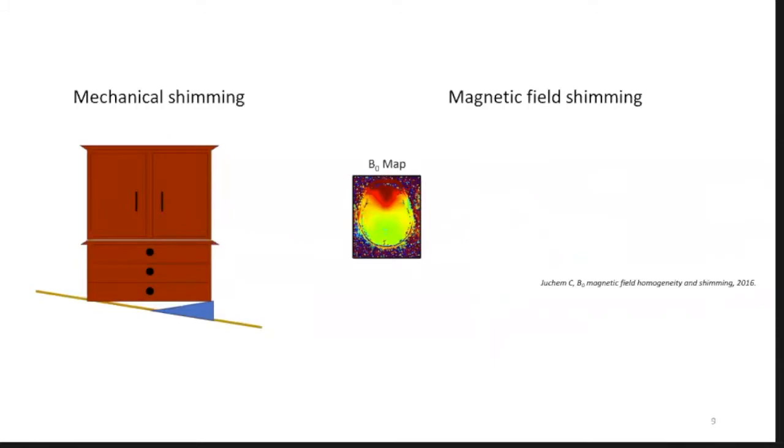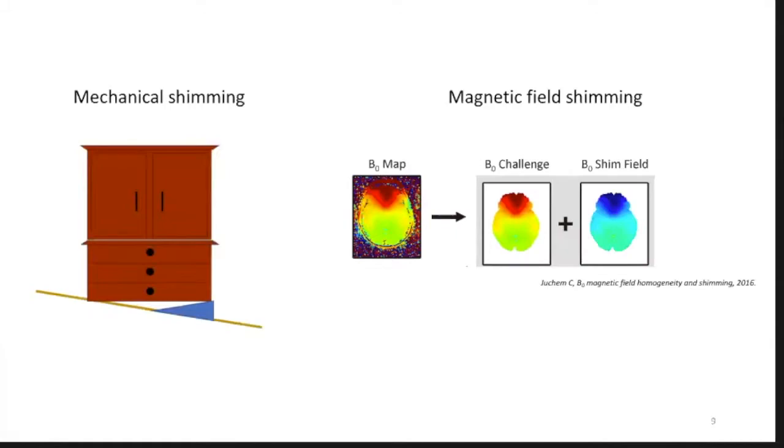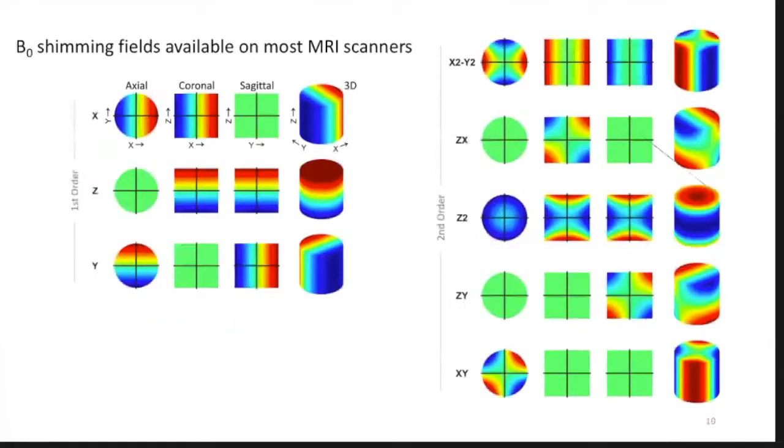It's the same thing in the body. The air tissue interface in the sinuses creates this very characteristic off-resonance hot spot in the frontal lobes, which is a very interesting area for neuroscience. So you have a B0 challenge. You then try to generate a compensating magnetic field that'll cancel out that B0 challenge and give you a flat magnetic field. So how do you do this? Well, you need coils to generate the fields. And in the scanner, there's already eight shim terms built in. You have the first order shims on the left and the second order shims on the right. The first orders are just your linear encoding gradients.